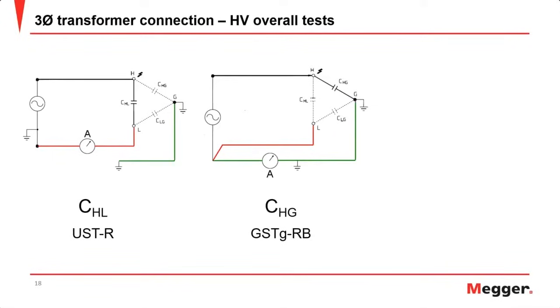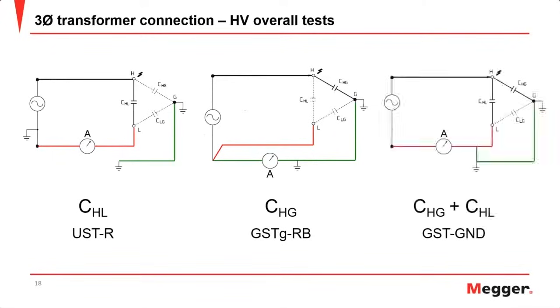And then finally, the last measurement, the GST ground. You'll see in this example that the ground path is connected directly to the ammeter along with the red lead. So in this case, we are measuring the sum of UST-R and GST guard RB to give us our GST ground measurement. And when you look at capacitance, you will see that the first two values, for UST-R and guard RB, will add up to the GST ground measurement, or fairly close.